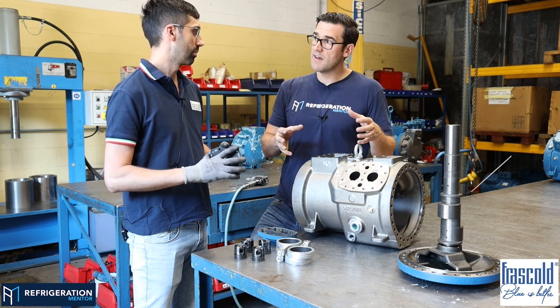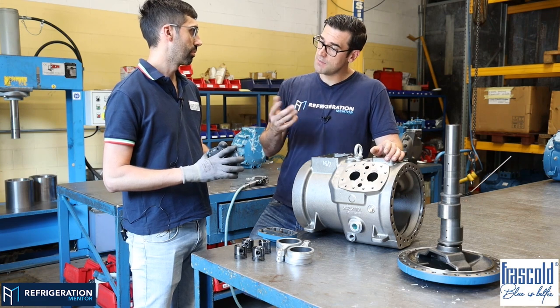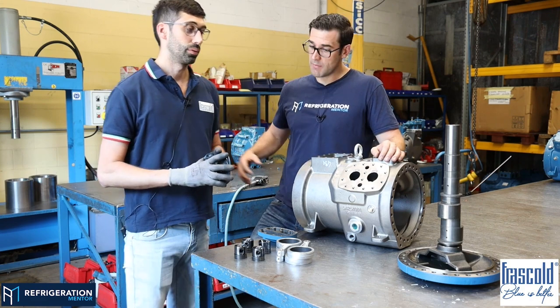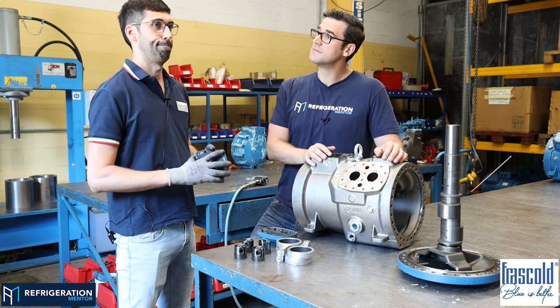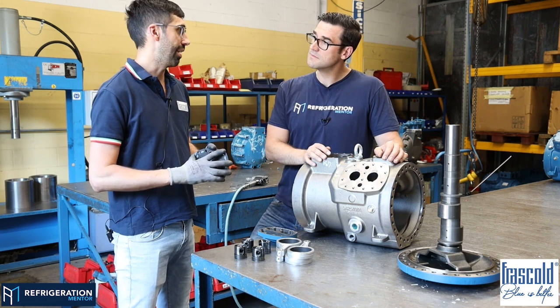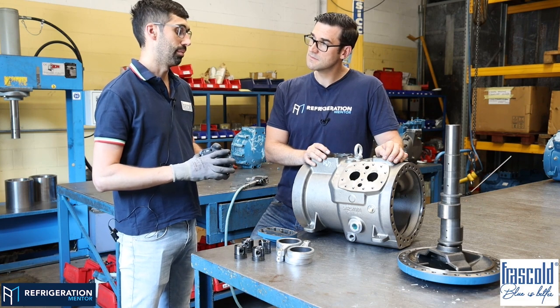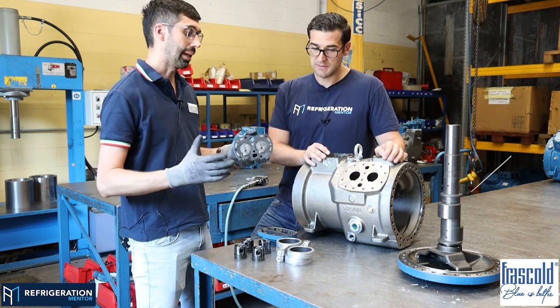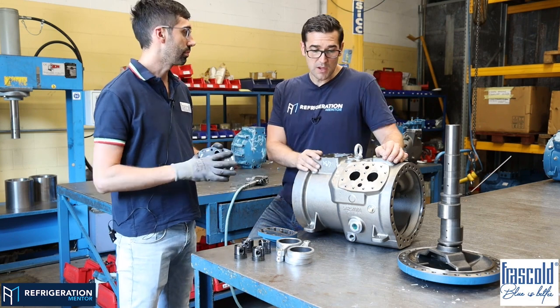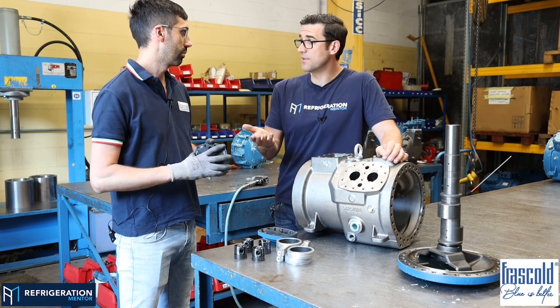And then all of a sudden you have a defrost and then all that oil comes back. Could that be a potential to smash the valves coming from the suction line, and you got all this oil entrained in the gas? Every sudden event and big transient can bring liquid return inside the compression chamber. That can be an example. Okay, cool. So that is smashing the suction valve. So that could be some examples of breaking that.